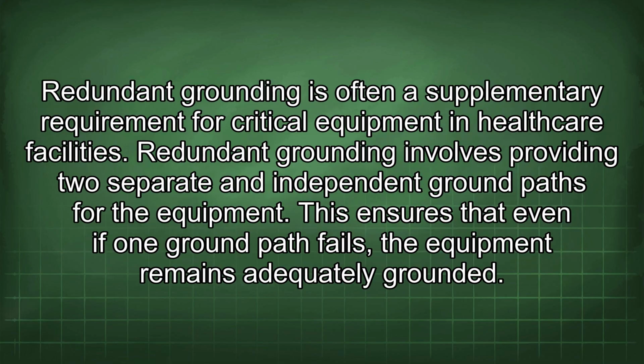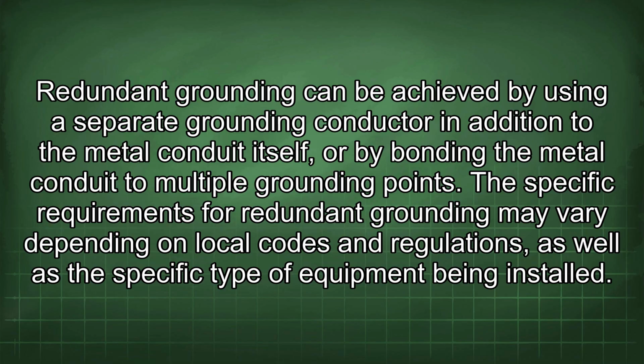Redundant grounding is often a supplementary requirement for critical equipment in healthcare facilities. Redundant grounding involves providing two separate and independent ground paths for the equipment. This ensures that even if one ground path fails, the equipment remains adequately grounded. Redundant grounding can be achieved by using a separate grounding conductor in addition to the metal conduit itself, or by bonding the metal conduit to multiple grounding points.